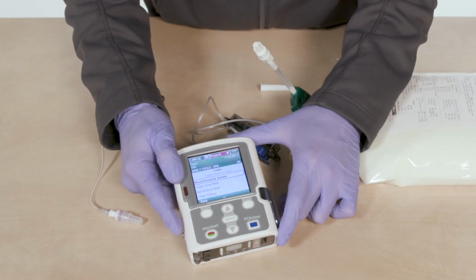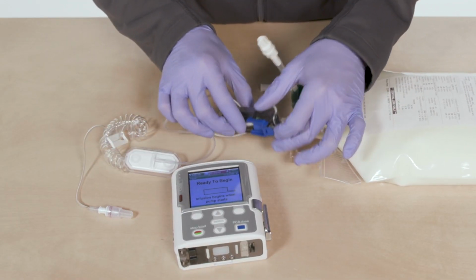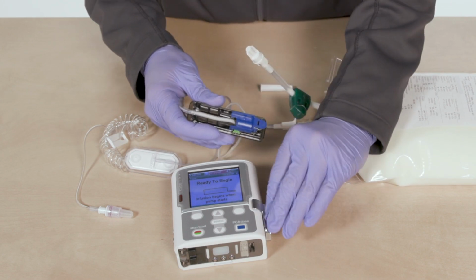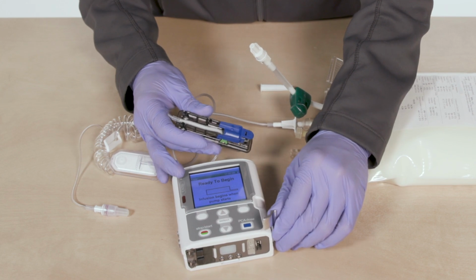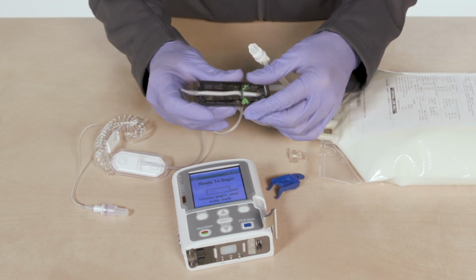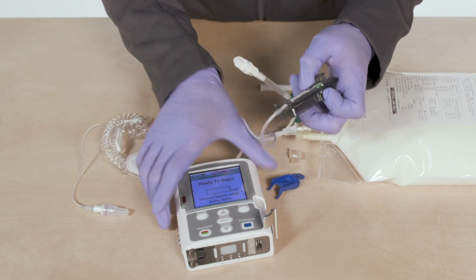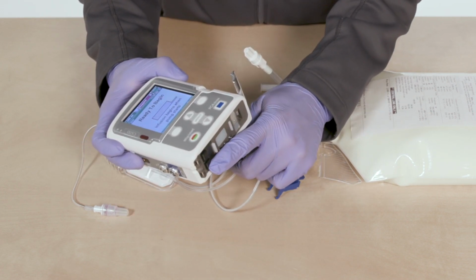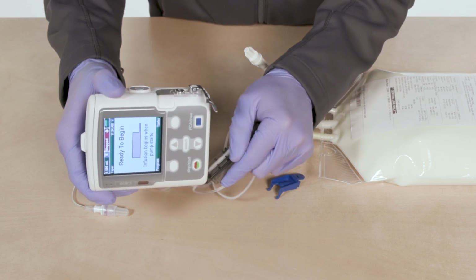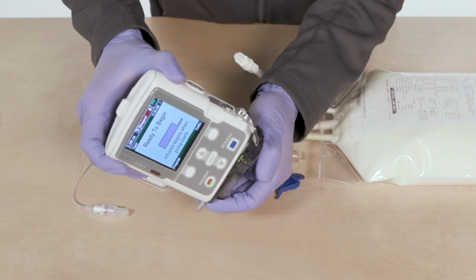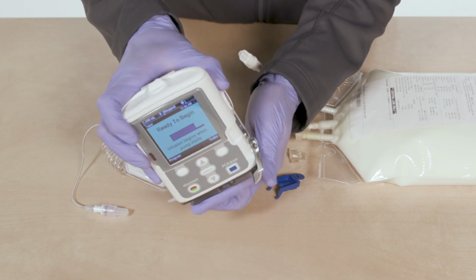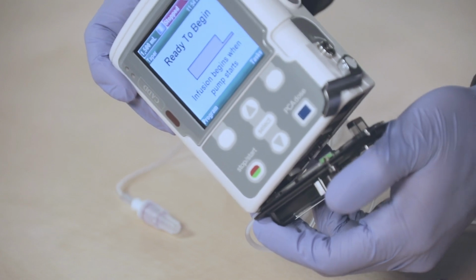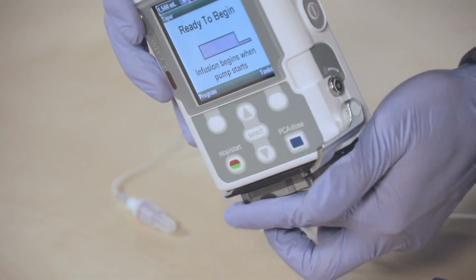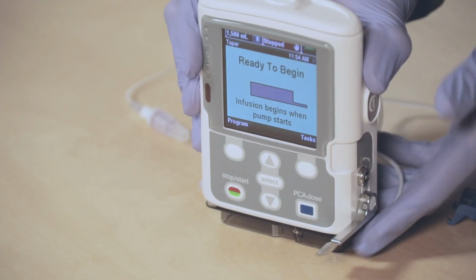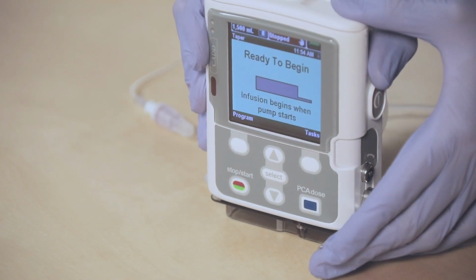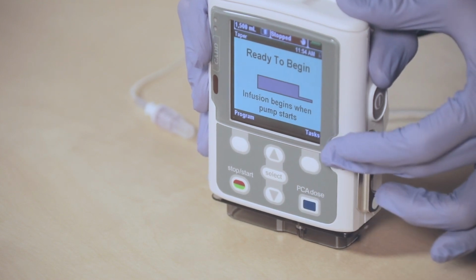To load the new cassette on, first make sure that the silver lever on the right side of the pump is pulled down. Now, place the 2 hooks on the left side of the cassette onto the 2 metal bars on the bottom left of the pump. This will create a hinge point. Now hinge the cassette into place, moving the square peg on the right of the cassette into the square hole on the bottom right of the pump. It is easiest to hold it in place by placing the cassette and pump on a solid surface, such as a table. Maintain pressure on the pump and move the silver lever back to flush with the pump.